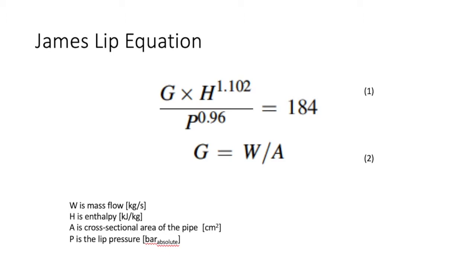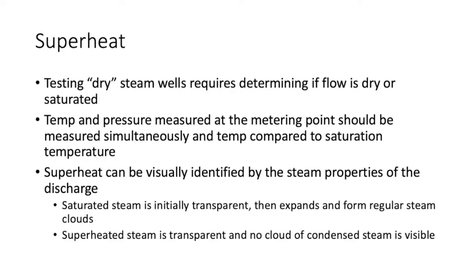The James equation (equation 2) calculates the flow rate G by dividing the mass flow by the cross-sectional area of the pipe. Enthalpy can then be calculated once the flow rate and lip pressure are known using equation 1. Testing dry steam wells requires determining if the flow is dry or saturated. Temperature and pressure measured at the metering point should be measured simultaneously and compared to the saturation temperature. Superheated steam is transparent with no visible cloud at the wellhead, while saturated steam is initially transparent and then expands into regular steam clouds.